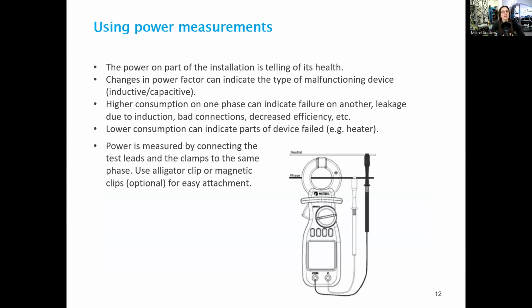The next ability of the clamps that can be very well used in troubleshooting is the power measurements. Power consumption, or power use, is one of the very essential functional tests for devices or parts of installations. Power within the specification usually means that there are no issues that need resolving. However, changes in either power consumption or power variables can be very indicative of a type of malfunction happening. So power factor can indicate the type of problematic device or the part of the device.